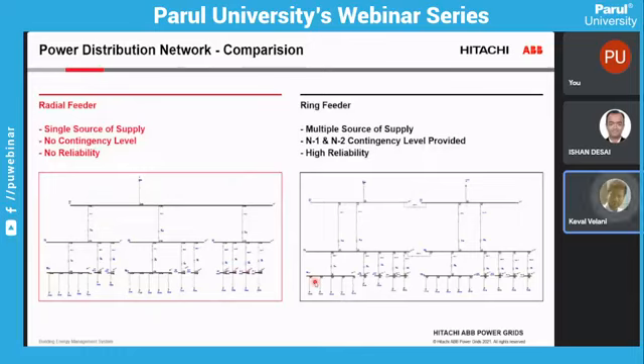This is a comparison of radial feeder and ring feeder. Here you can compare: single source versus multiple source, no contingency level meaning no second source of supply and no reliability during faulty condition or maintenance, versus n-1 and n-2 contingency level provided with a highly reliable system.